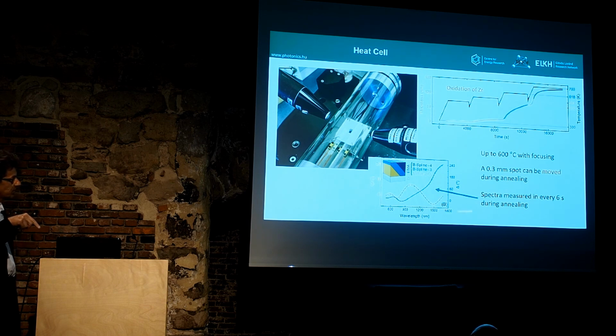You can see here part of the spectrum. It's even larger, from 190 nanometers to 1700. So that's 1,400 data points measured each second, basically. If you evaluate the spectra like this, each one becomes 1 point in this time-dependent measurement graph. So each point here represents 1,400 data points, fitted. From this fit you can determine the thickness, and follow the change of thickness as a function of time.